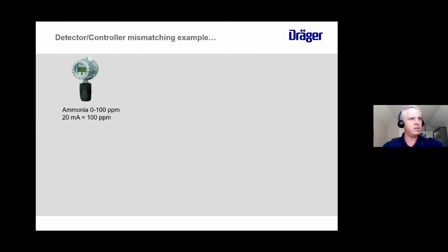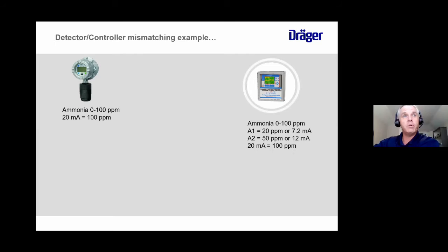So you buy the detector and the sensor and you range it to 0 to 100 ppm. So you go to the old style controller, which is in this example a Draeger Guard Plus, right? And so you set the controller up to basically read the same thing. So you tell the controller, hey, when you see 20 milliamps from the detector, that actually corresponds to a value of 100 ppm. So at the controller, you set your alarms.